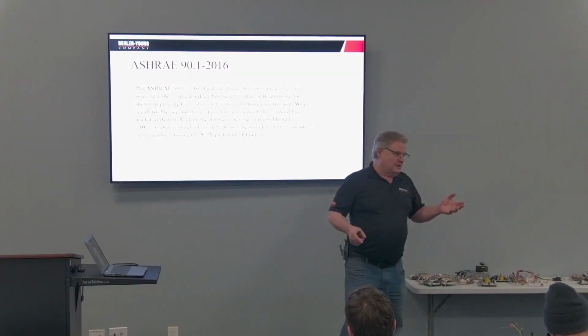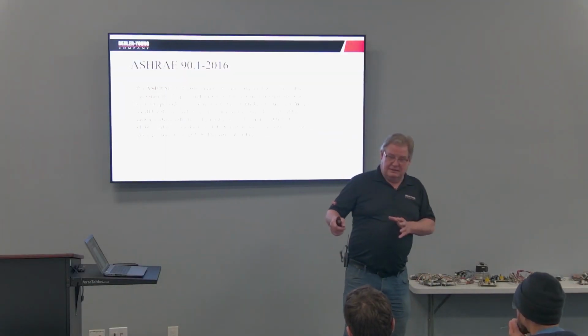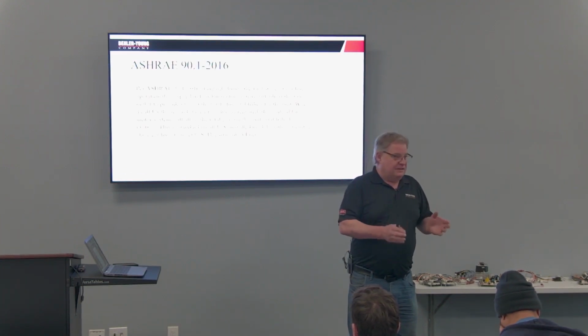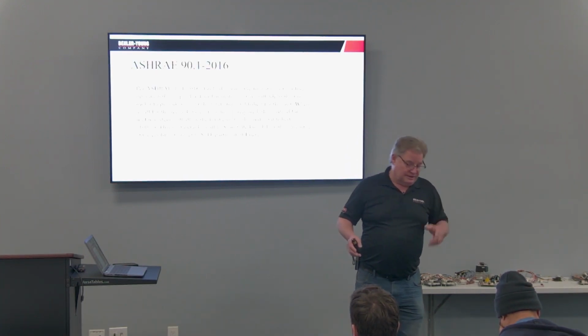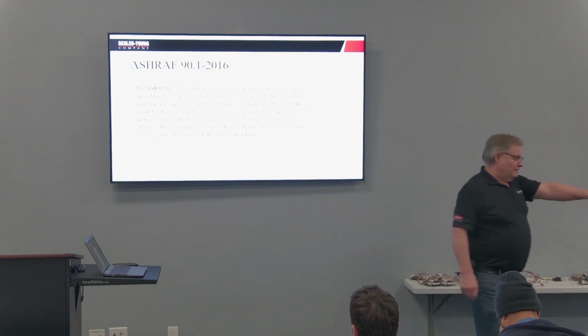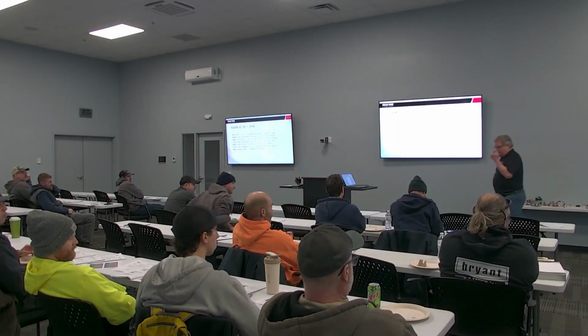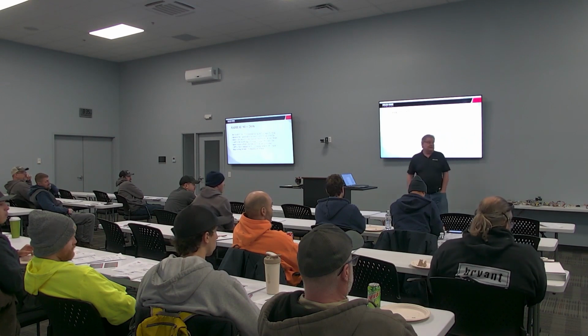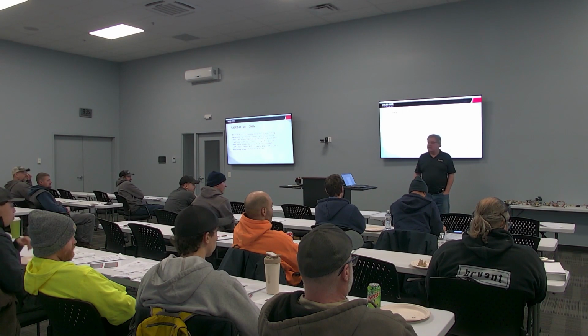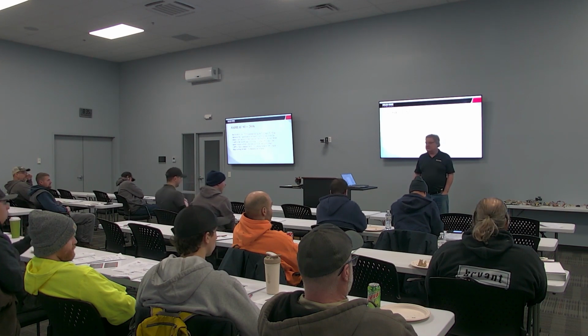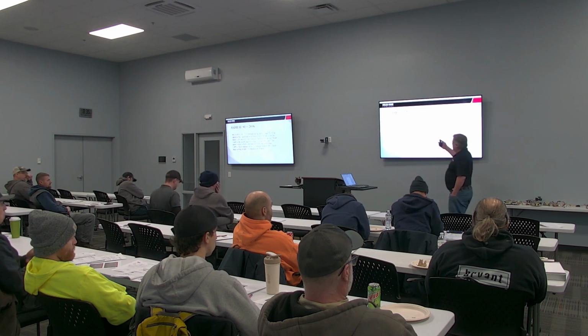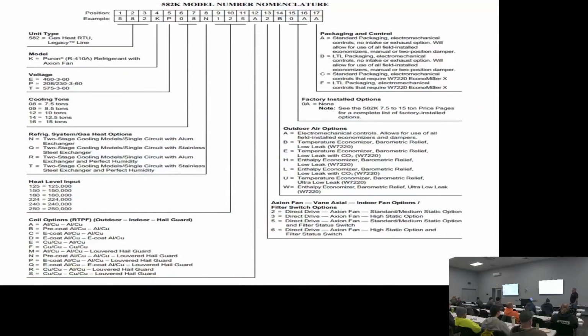So when you walk up on one of our rooftop units, if it's the older 580, going back to about 2017, it's got a VFD in it. That VFD is there to make 2-speed. We'll get to that VFD. This blower here, the Axion or Bluon, as our Carrier brothers would call it, is running on a DC signal, but it has 2 speeds. It's running at low speed for circulation and first stage cooling, high speed for heating and second stage cooling. So this is the whole reason that was all done. When you're wondering why we did all this? Well, because the government said so.